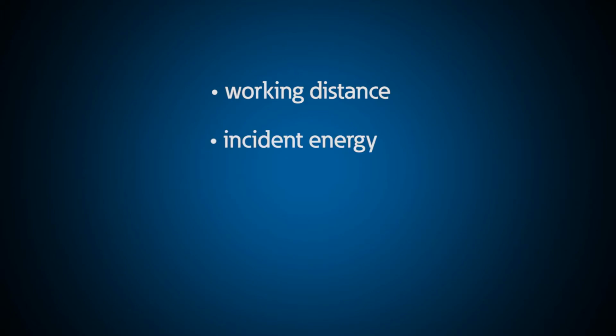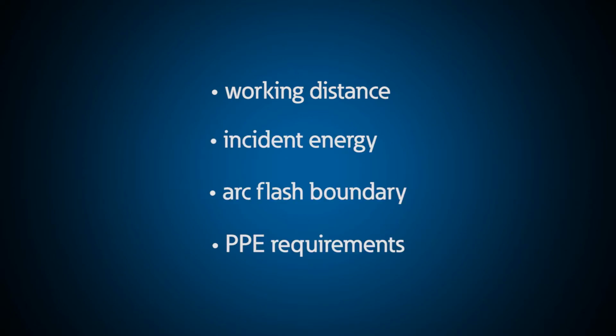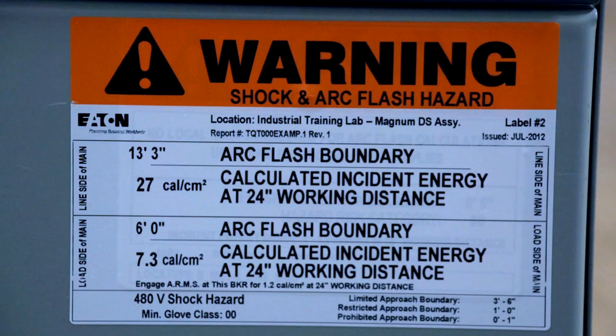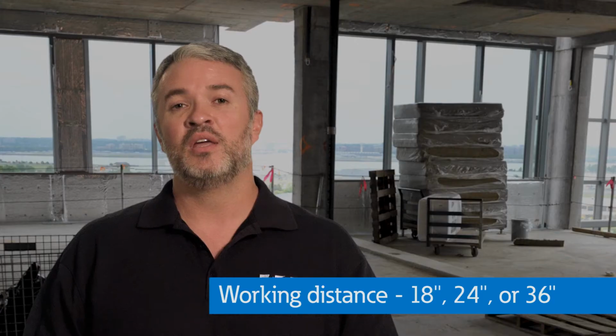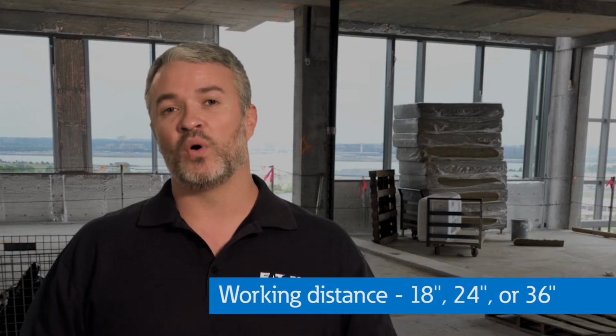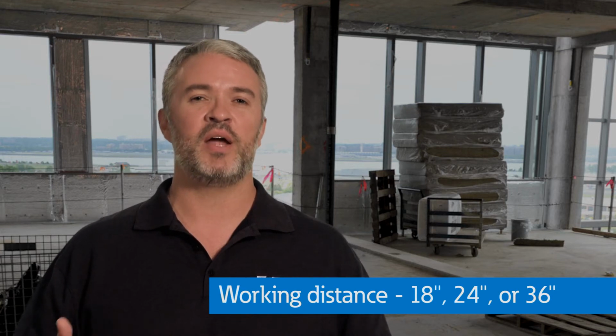Some of the most misunderstood things related to arc flash are working distance, incident energy, arc flash boundary, and PPE requirements. A good understanding of the arc flash label helps to clarify most of these points. Looking at the label, the working distance is defined as the distance from your face or torso to the energized conductors. This can be 18 inches, 24 inches, or 36 inches, depending on the voltage level. This is roughly an extended arm's length.